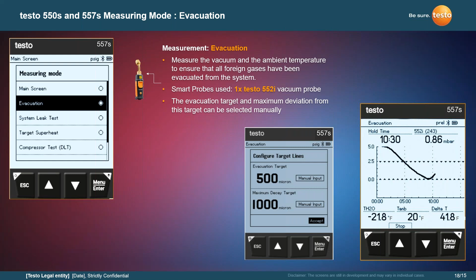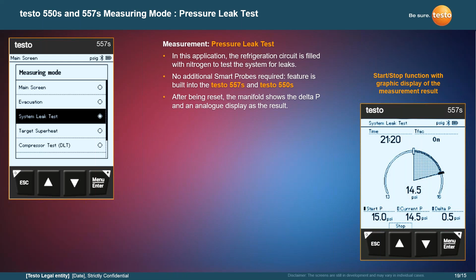So again, this can be used by itself. It can be used through the manifold, and you can read your information through the manifold, and you can also read it through the smart application as well. So pressure leak test kind of coincides with your vacuum test as well. You can do this. Again, no probes are really needed. You just have the 557 and the 550, and everything's built into them to do this type of measurement, so you can see where you are with your nitrogen. You put nitrogen in, positively fill it, and then you look and see, over a certain amount of time, what kind of decay you may have in that leak check.